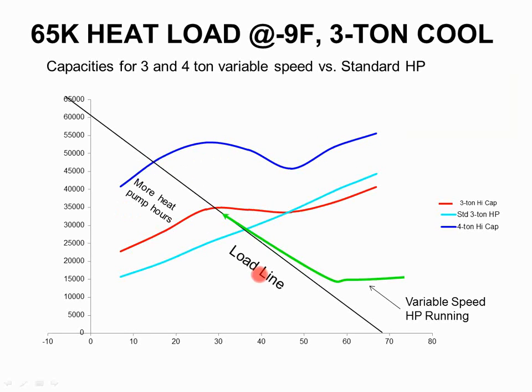Right, but for this one, if I put the regular 3-ton in, at 36 degrees outside, that's where my balance point would have been. If I put the variable speed 3-ton in, now the balance point's 28 degrees. If I put the variable speed 4-ton in, my balance point is, we'll call it, 14 degrees. Right? So just by upsizing from a 3 to a 4-ton, I can get more capacity. I'm not saying you should randomly start upsizing heat pumps, but if it's a variable speed, variable capacity piece of equipment, you have the ability to do that.